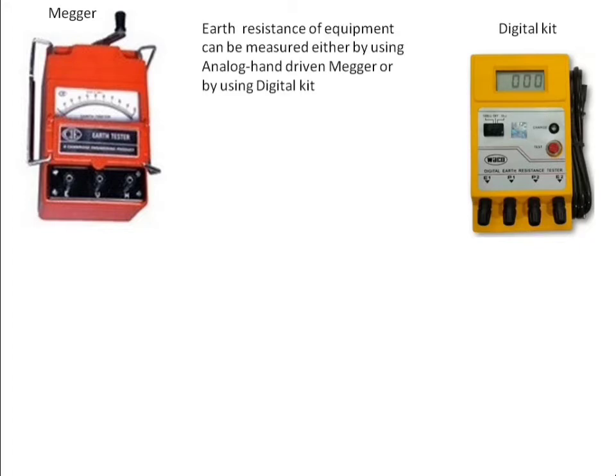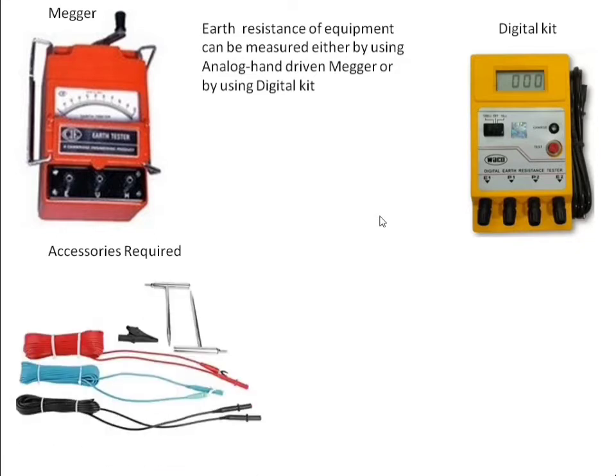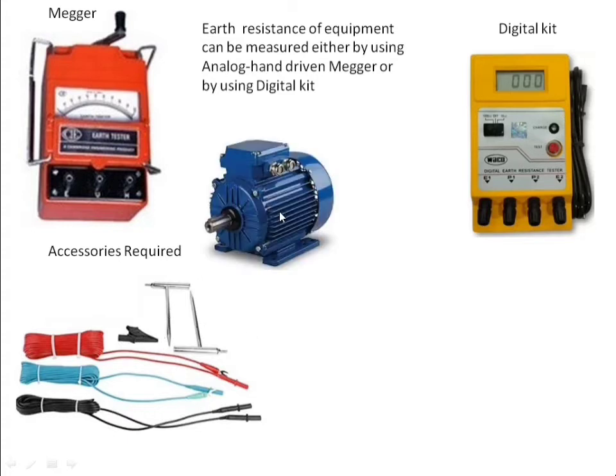Both devices consist of a voltage source to produce a voltage spike. The conventional meter consists of a hand-driven tiny generator used as a voltage source, while the digital kit consists of rechargeable batteries as voltage source. Because we require a voltage spike for measuring earth resistance by circulating current through the ground. It consists of simple accessories: 3 sets of wires, 2 earth rods of 1 feet length and clips.